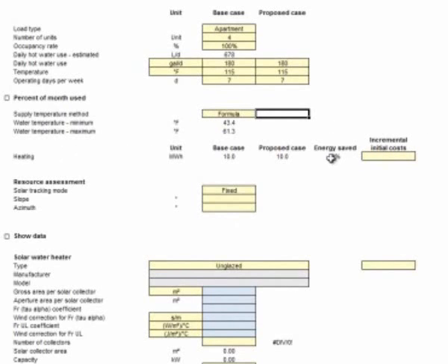Now we haven't saved any energy because we haven't decided on what to select in here. What we're going to do first is just very roughly. Now, there's some things that I've learned over the years, and I'll just relay them to you now, that you can get as involved or not involved with as you want. But simply stated, for every gallon that we wish to store is about 1 square foot of collector space. So, for example, if I have a tank that I need to store 180 gallons, I should have a solar thermal system that has about 180 square feet.